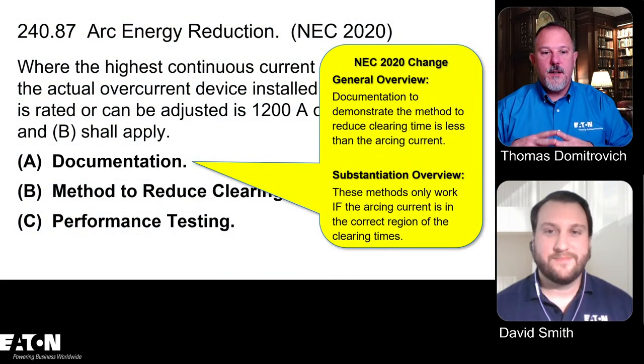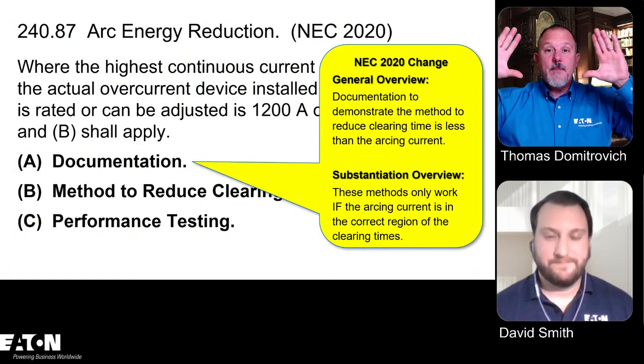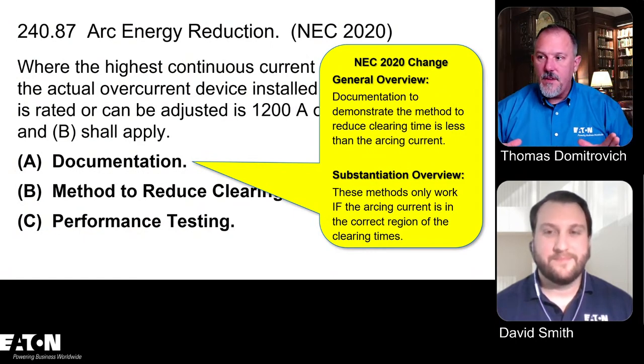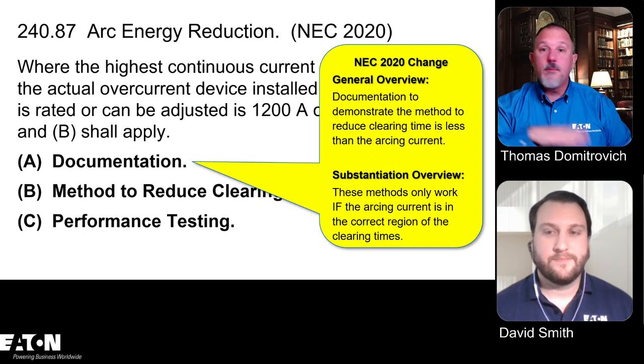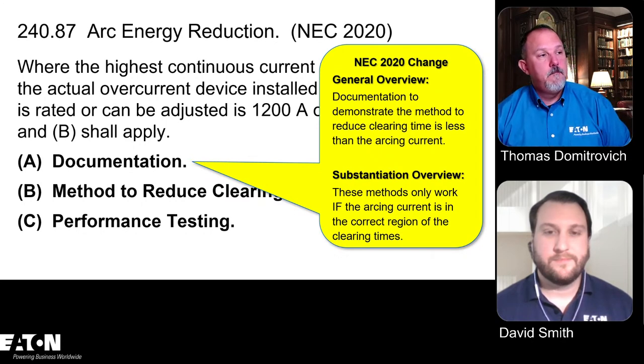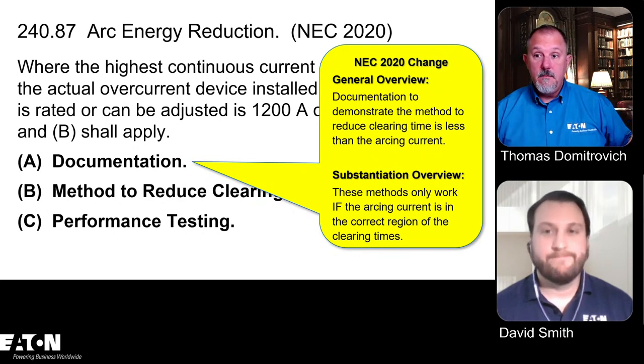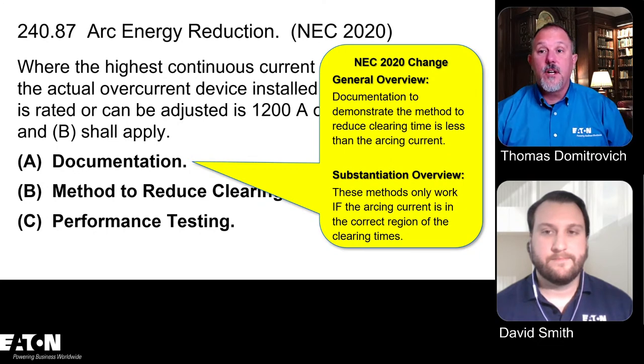All right. Documentation. If you think about the requirements, A, B, and C. We talked about the parent text. I think we have a good feeling that if it's less than 1,000 volts, so 480 volt systems, or 600 volts if you're in Canada, and you can adjust that circuit breaker to 1,200 amps or above, that's pretty much it. It doesn't say if it's AC or DC. So if you have a 1,200 amp DC breaker, you're into arc energy reduction. That gives you the flavor for the requirement. Now we're going to get into documentation.